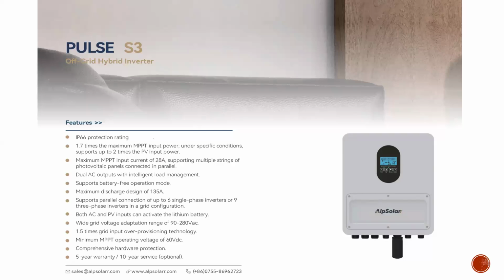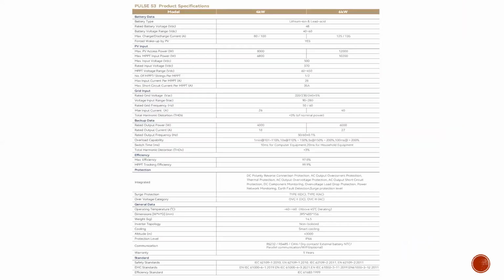So the next slide talks about the power specifications and datasheet of the system, which I will not take much time on since I've said a little on that. What I'll just talk about there is that it is well protected. It has a lot of protection. If you look at the protection side, it has DC reverse polarity protection. That means when you interchange your PV input cable, the negative to the positive, the positive to the negative, there's protection on the inverter to forgive that mistake, right?